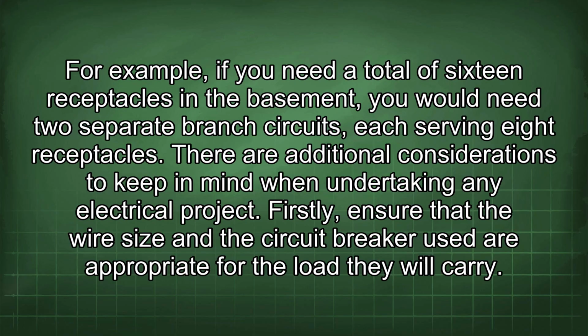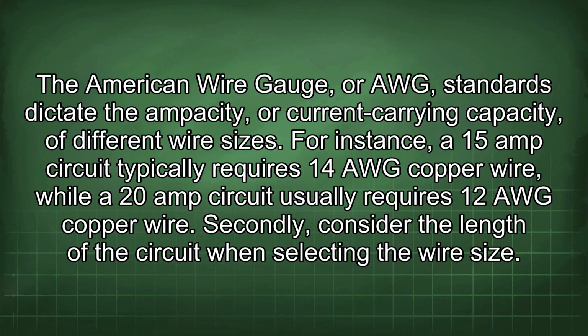For example, if you need a total of 16 receptacles in the basement, you would need 2 separate branch circuits, each serving 8 receptacles. There are additional considerations to keep in mind when undertaking any electrical project. Firstly, ensure that the wire size and the circuit breaker used are appropriate for the load they will carry. The American wire gauge, or AWG, standards dictate the ampacity, or current carrying capacity, of different wire sizes.